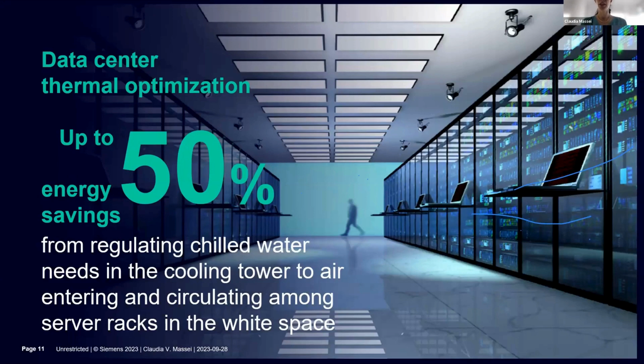Thermal optimization means you look at everything from the cooling tower, where the air is cooled down and where basically the temperature of the air entering the data center is determined, as well as all the inlets and temperatures within every corner of your data center. Depending on how the air flows through the data center, some corners will be colder than others, and you need to make sure the ones that really need to be colder are the coldest, and the ones that don't need it are not.